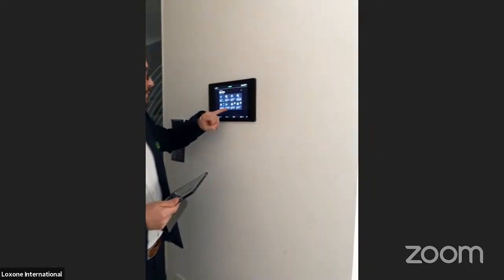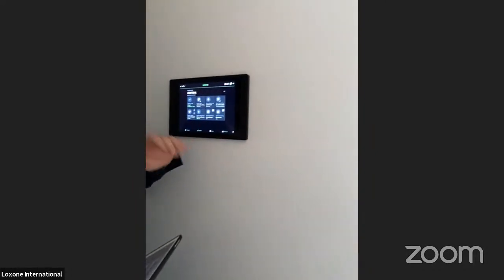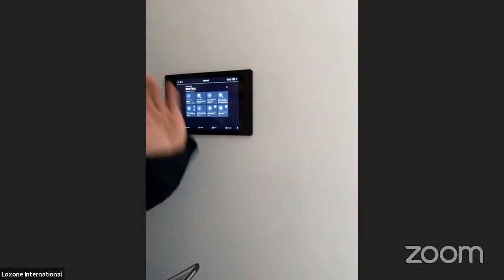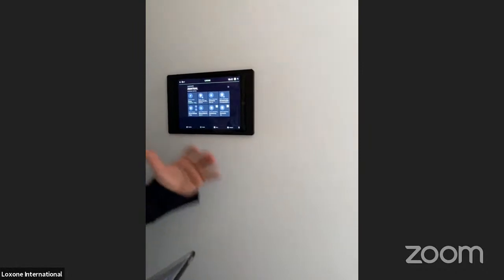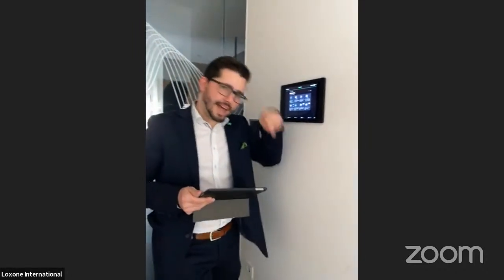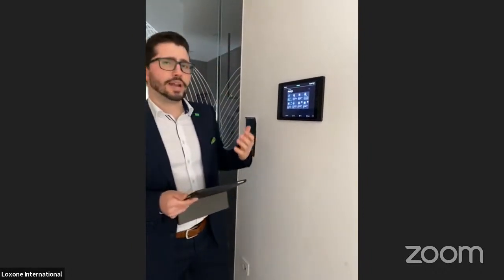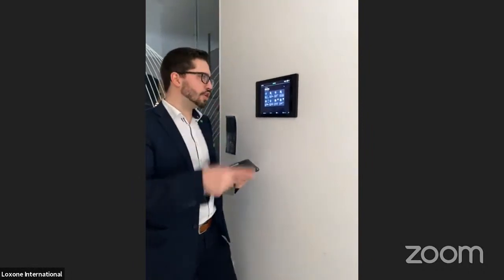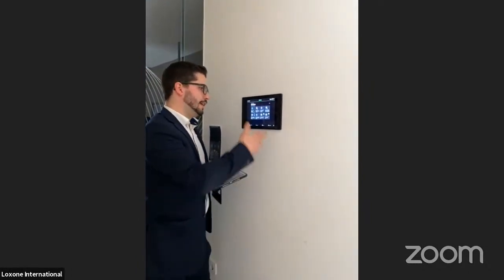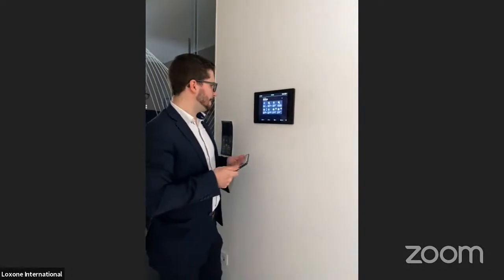You see here, there is also something like storm protection, especially for outside shading. It's important to understand that if there is a wind, a storm coming, the blinds will be damaged. So not only do we have a local sensor measuring the actual wind speed right now, but also we have the weather forecast. So we know if a storm is coming in 1 hour, then let's not wait for the wind speed meter to turn on really fast. Then proactively put them up, okay?